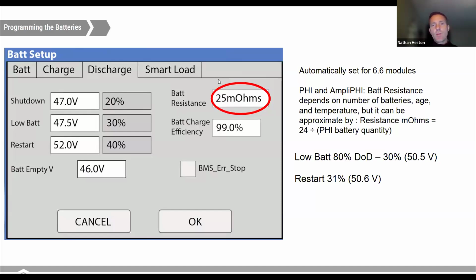Battery resistance. The battery resistance overall should be about 8 milliohms for a 3-stack of batteries. It's essentially the resistance of a single battery divided by the number of batteries in your bank. So for a 6.6, that's 20 milliohms divided by the number of batteries. For 3.8, that's 24 divided by the number of batteries. But if you've got a communicating battery, this will be set automatically.